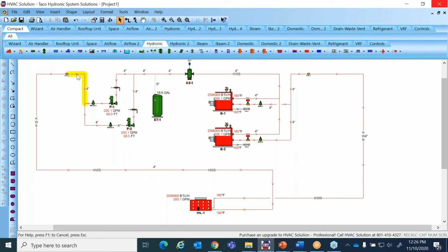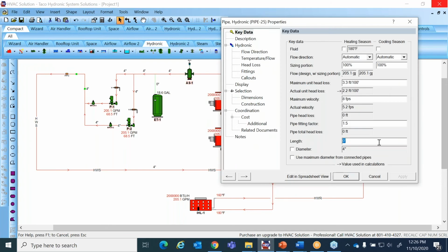If I click on this piece of pipe, or any piece of pipe, it shows how it's sizing the pipe. Normally you'd need charts for velocity and flow through each piece of pipe, but all of that information is built into the software. Based on the flow, maximum unit head loss, and maximum velocity, it has selected a 4-inch diameter pipe, and those are the values it's using. Similar to the other flexibility, you can change those values as well.